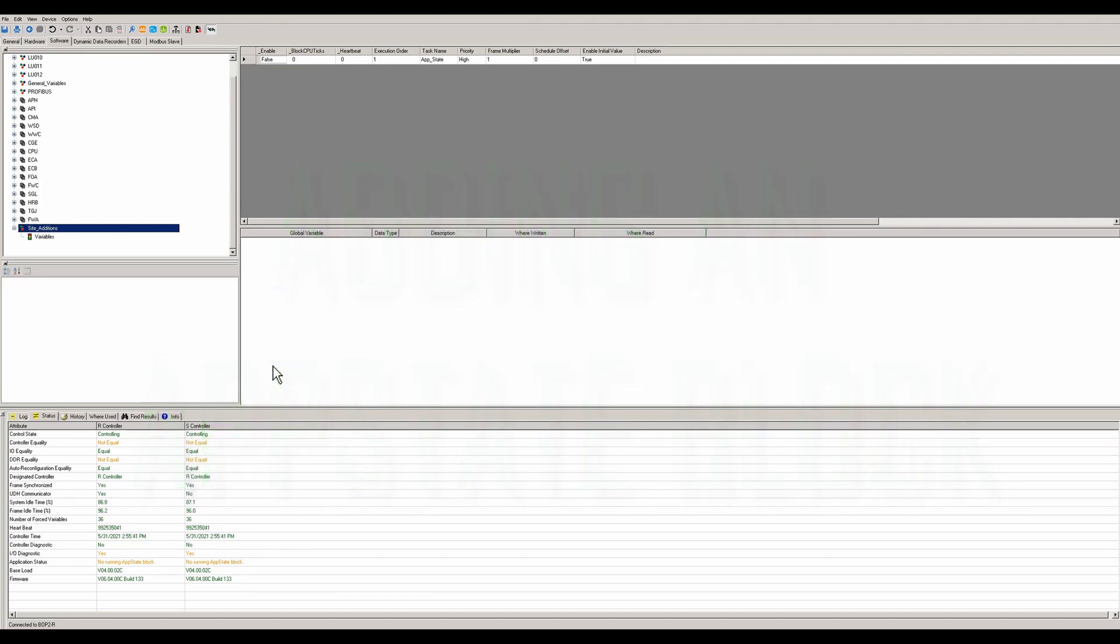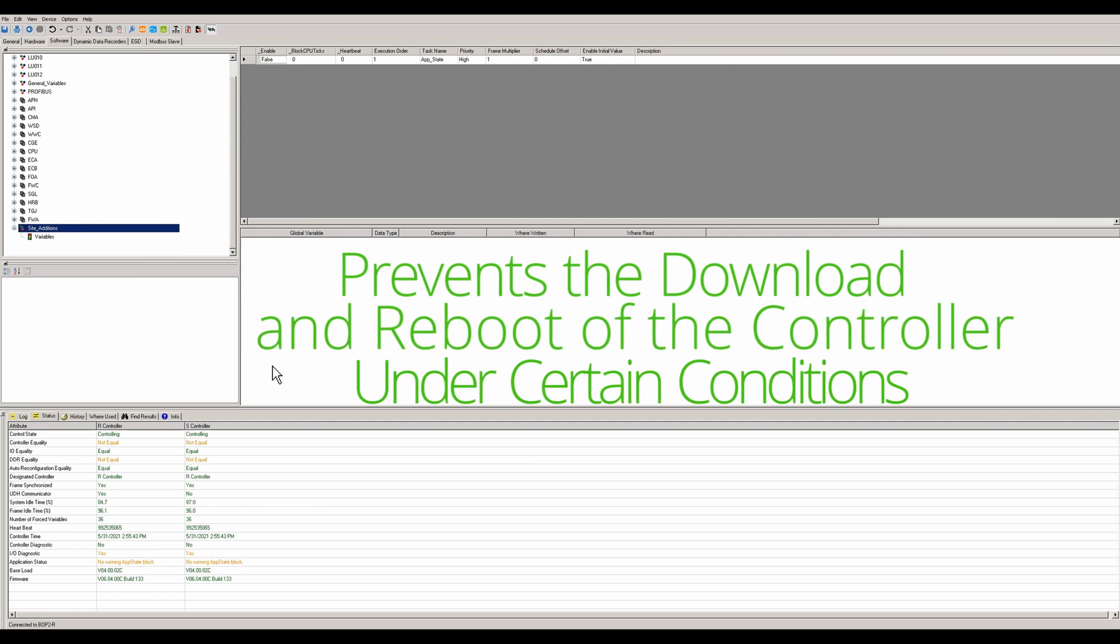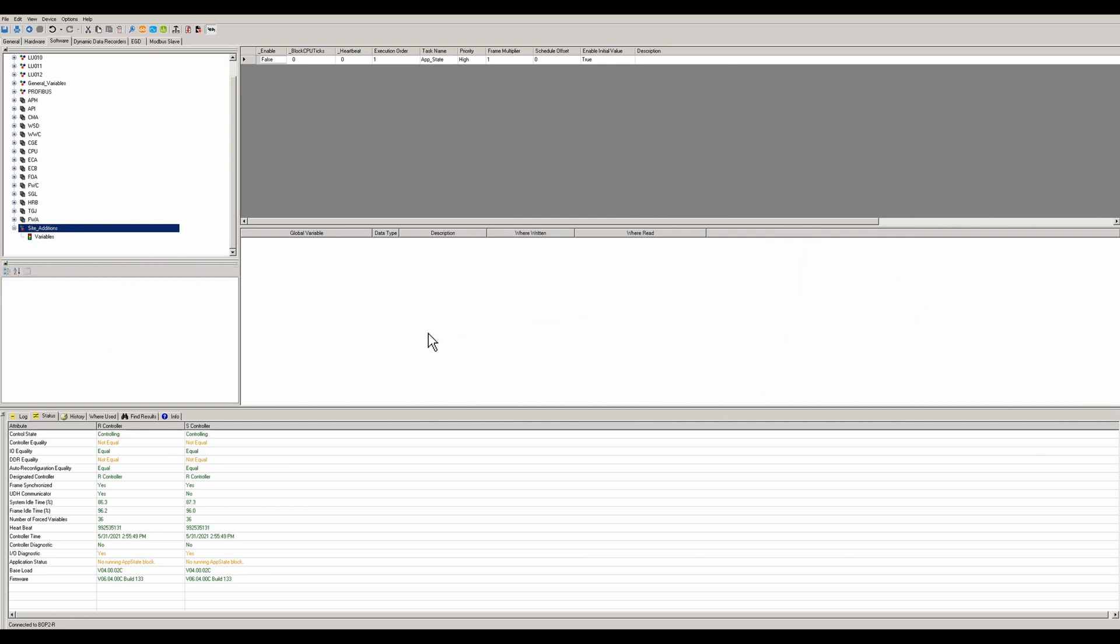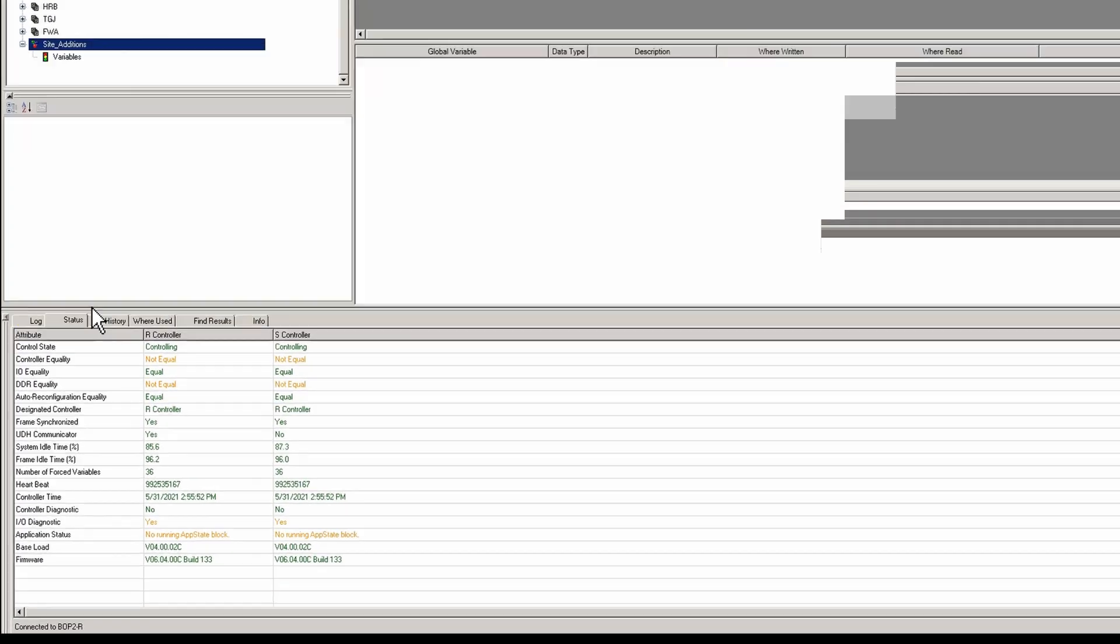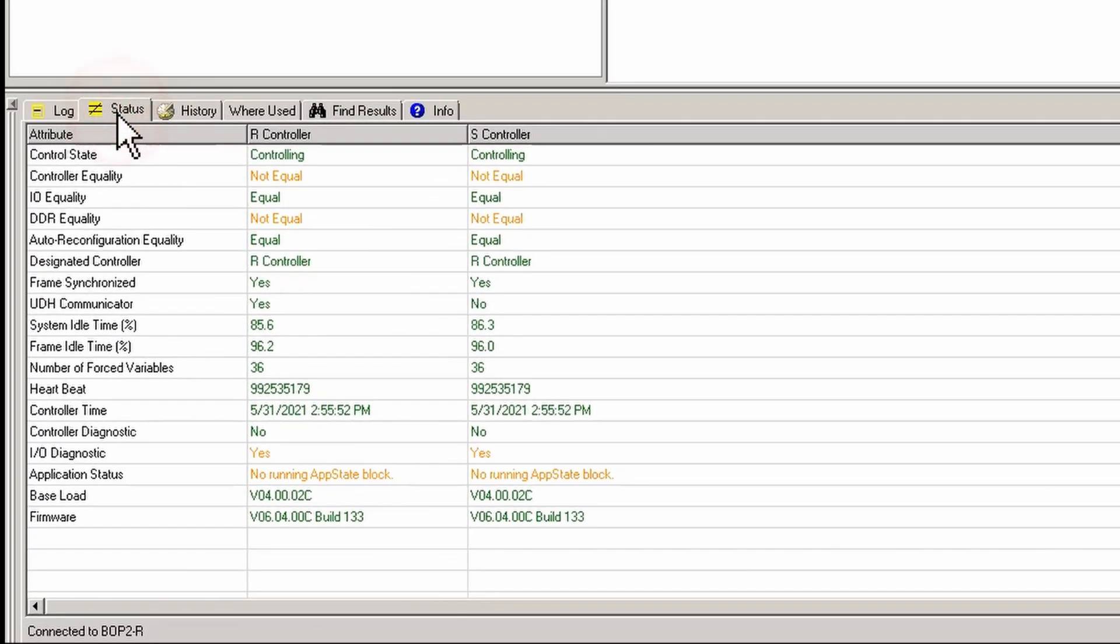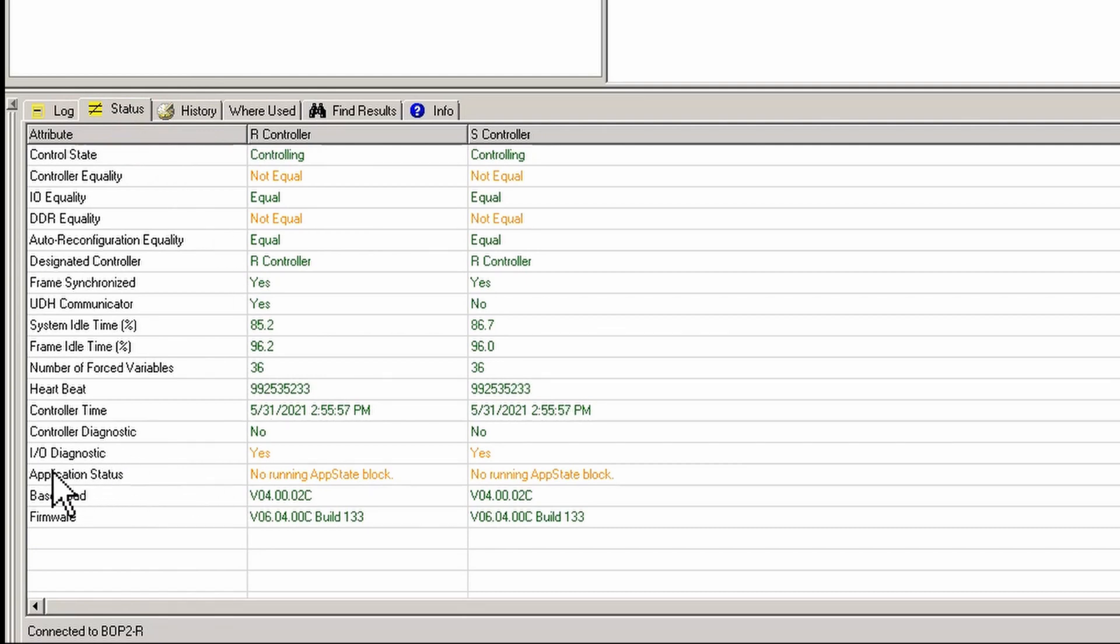We're going to add an app state block. An app state block is good because it prevents the download and reboot of the controller under certain conditions. When you go into a component and go to your status, you'll see there's an application status field that says no app state block, which means there's no app state block.